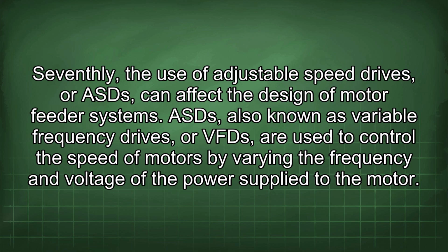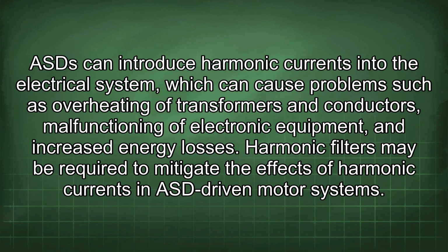Seventhly, the use of adjustable speed drives, or ASDs, can affect the design of motor feeder systems. ASDs, also known as variable frequency drives, or VFDs, are used to control the speed of motors by varying the frequency and voltage of the power supplied to the motor. ASDs can introduce harmonic currents into the electrical system, which can cause problems such as overheating of transformers and conductors, malfunctioning of electronic equipment, and increased energy losses.